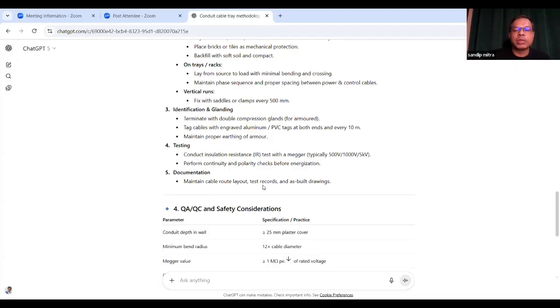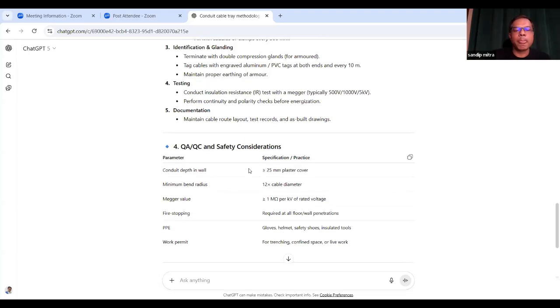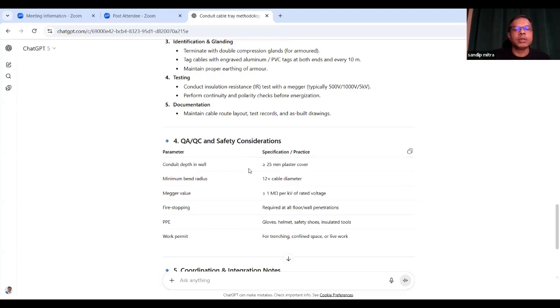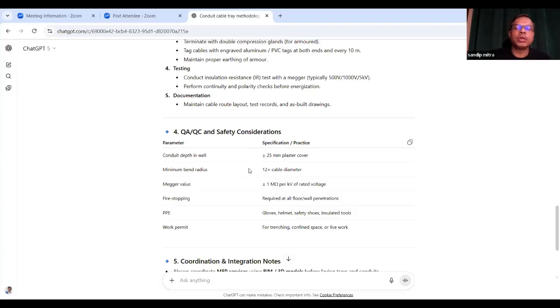Maintain cable route layout, test report, and as-built drawings as a documentation process. They need to follow quality assurance, quality control, and safety considerations - these are also part of the methodology. You need to mention all the parameters: conduit depth in the wall, minimum bend, Megger value, fire stopping, PPE.